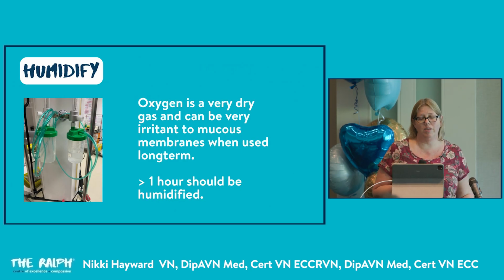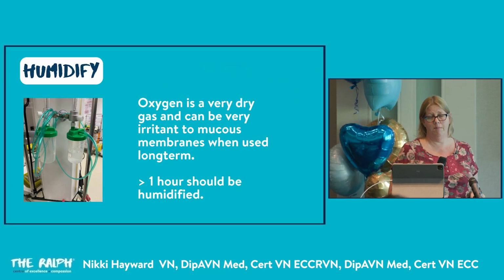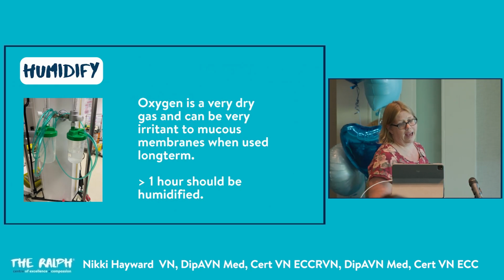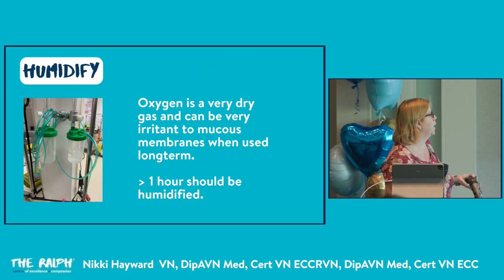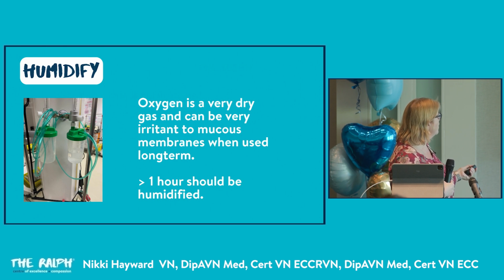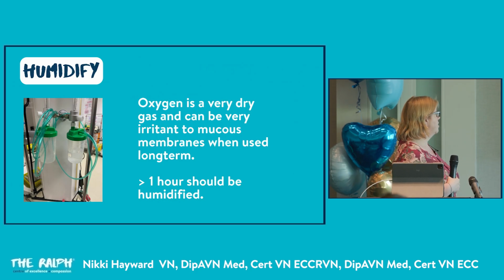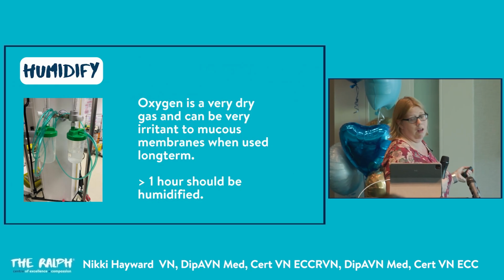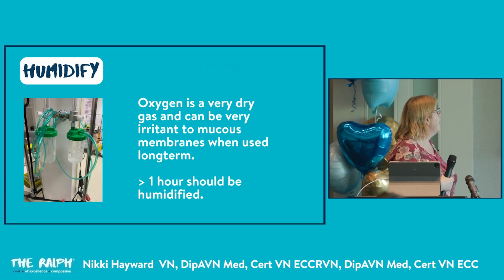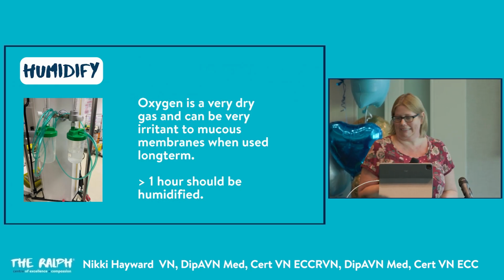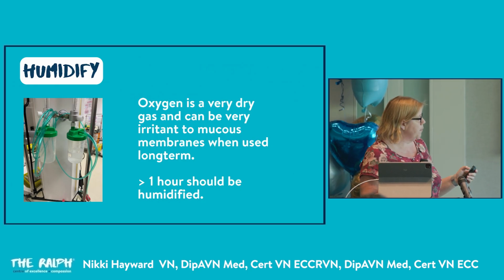Before we go into the different ways we can deliver oxygen, one thing to mention is humidifying oxygen. Oxygen is a very dry gas and can be very irritant to the mucous membranes, especially when used long term. If it's less than an hour in a really quick emergency, then it's fine. But anything longer than an hour needs to be humidified. We basically use bubble humidifiers. I don't know if you can see it here, but there's a line across here. This has water in. Deionised water, sterile water, anything like that is absolutely fine. We turn the oxygen on here, it comes through, bubbles through the water, and then comes out through this green tubing to the patient. So the oxygen is now moistened, and they get humidified air. Again, you need to try and use the lowest amount of oxygen needed for the patient.